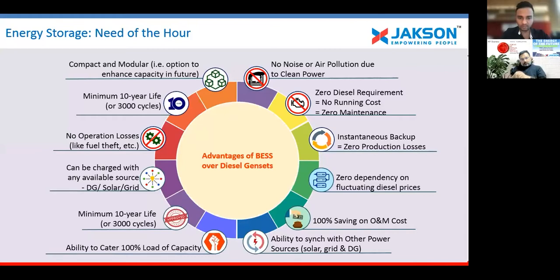It's compact and modular. You can buy one BESS and keep adding modules to increase capacity year on year. It has a minimum 10 years of life or 3000 cycles. There are no operational losses like fuel theft etc. It has a special unique feature that it can be charged with any available source - DG, solar, grid - whereas UPS can only be charged with grid.